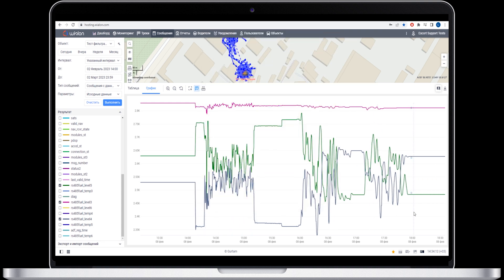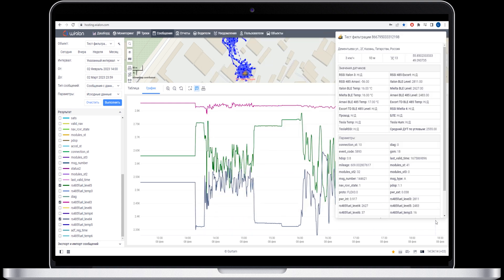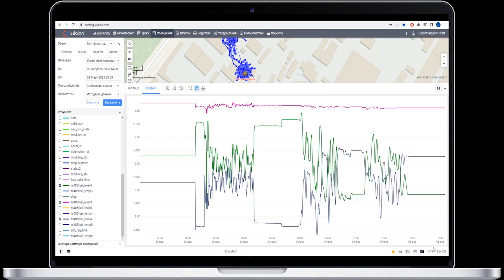But even given these limitations, we believe that the experiment perfectly explains why it is crucial to install the sensor in the center of the tank or as close to it as possible. Otherwise, you might need two sensors installed at opposite sides of the tank so they could compensate the level oscillations of each other.